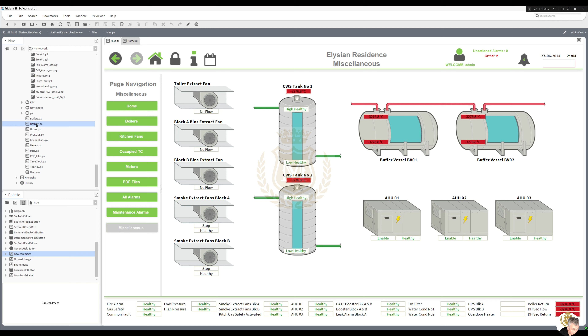Alright, come out of edit mode, go there, go there, go there, and I already had them there, so I could have just done a copy and paste. Right, why? Because we've moved the points. We did move the points, so that's the reason why they are now no longer working, because they've got the wrong values to UIs at the start, because of that email that I got. We moved them, so that is not going to be a DI3 in here. So UPS block common alarm is not going to find this.